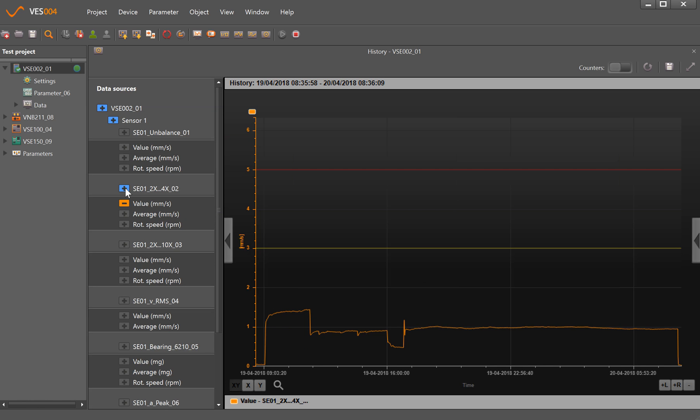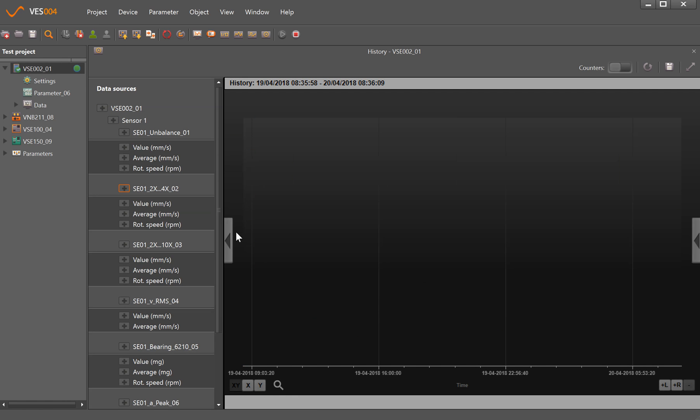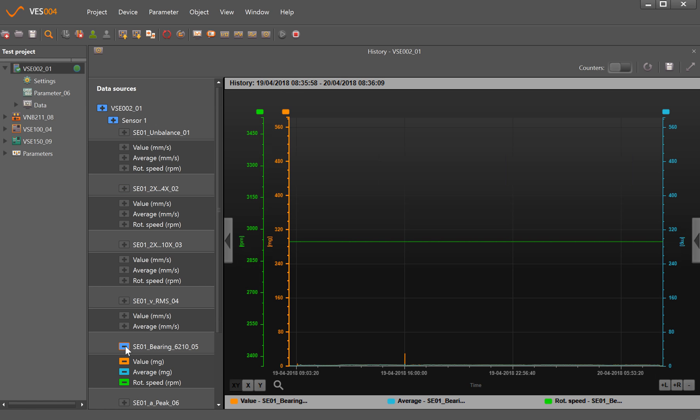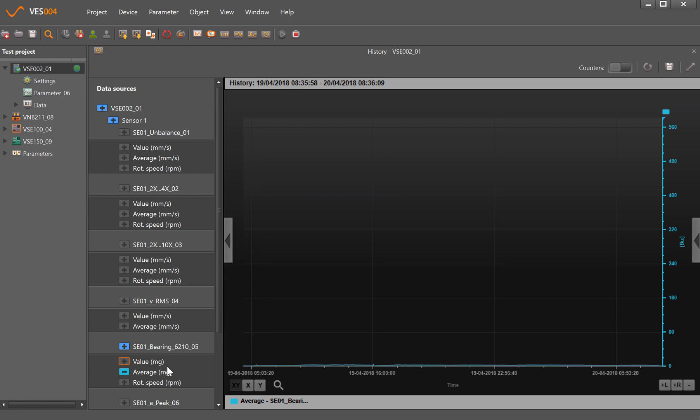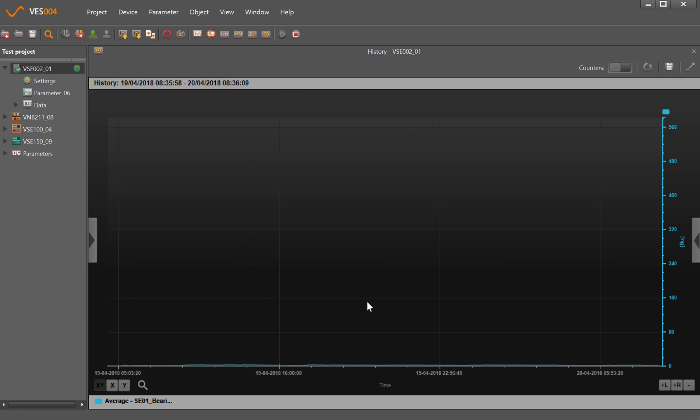If I just want to remove that, right-click, remove all from plot. And we'll maybe look at the bearing this time. So if I open up the bearing and we'll remove the speed as well because we're not so much interested in that because it's fixed speed, and we'll just maybe look at the average value this time. So if I want to remove the maximum value, now because this is on a small fan demo in my office, the levels here are tiny compared to a normal bearing in an industrial machine. If I click on the blue rectangle there, it will put in where the yellow and red limits are, and you can see about 250 and about 400 and maybe 50 milli g's.